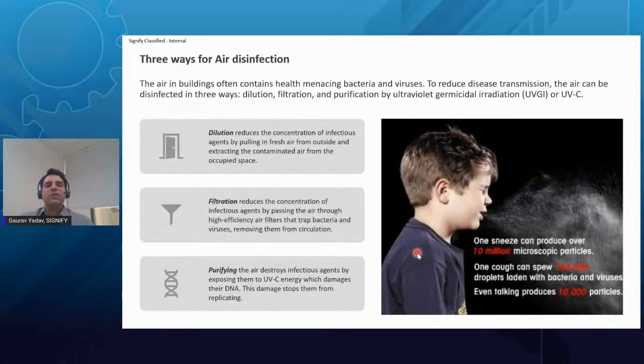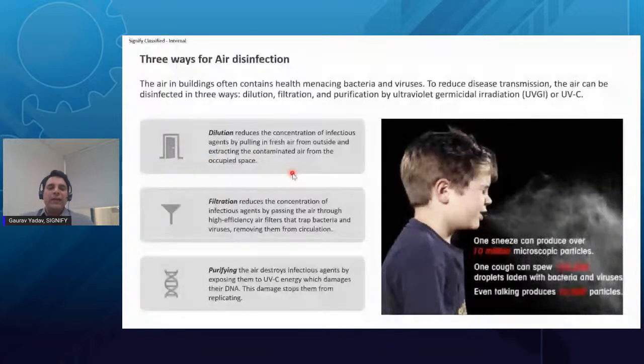So what are the different ways of air disinfection? How can you avoid all those bacteria and viruses? The first method is dilution. So what does it mean? You can pull fresh air from outside, or you can eradicate the infectious air from that indoor environment. So that is one way out. You can improve the ventilation system within the indoor environment. That is called dilution. Then second comes filtration.